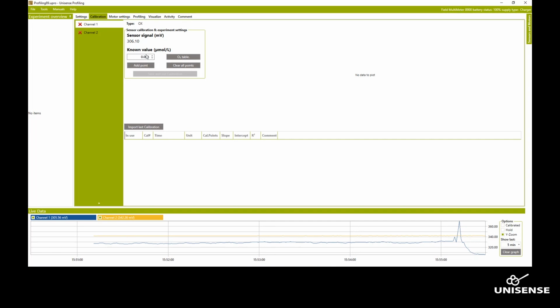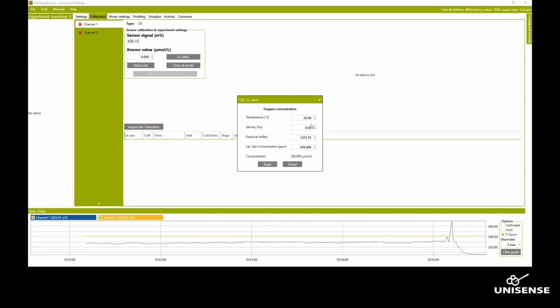Then I need to tell it what the concentration is in the calibration chamber, and for that I'll use the oxygen table. So 22 degrees, I'll enter that. I will be measuring in water with 22 per mil salinity, so I will enter this, so I get the correct conversion of partial pressure to concentration. Then you can also enter the atmospheric pressure, which will also affect the concentration in equilibrated water. This is the standard atmospheric pressure in millibar. I will not change that now.